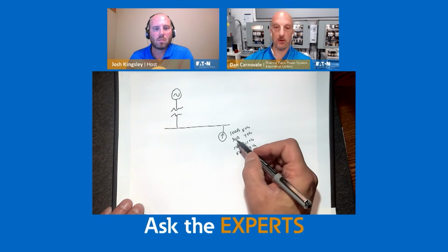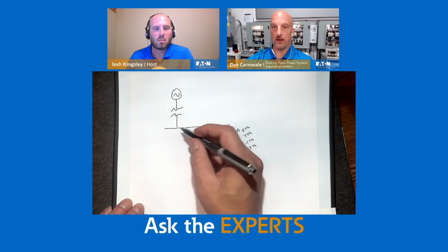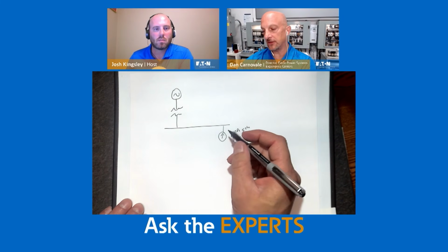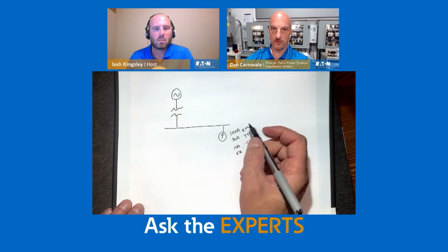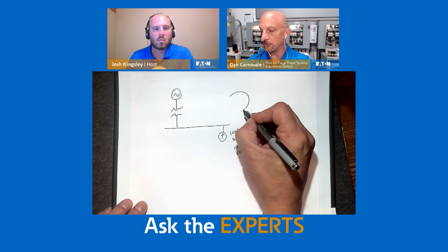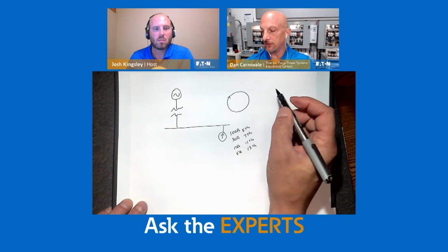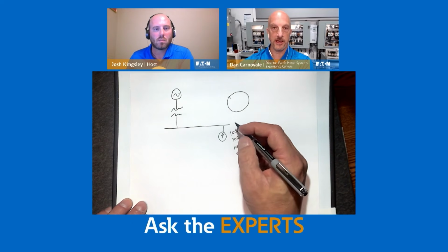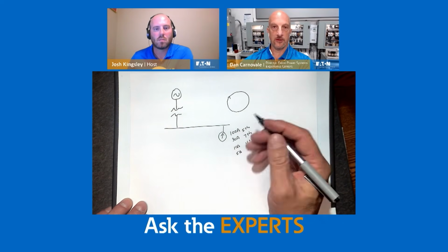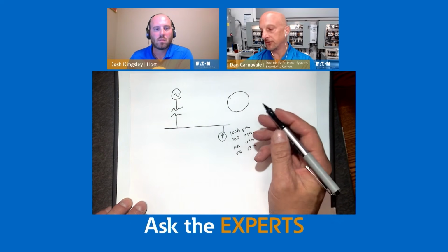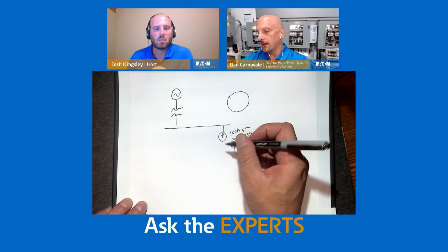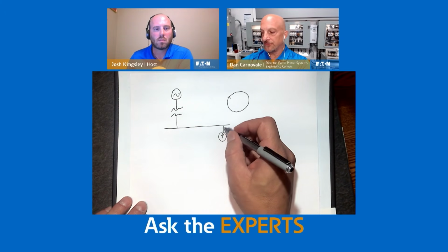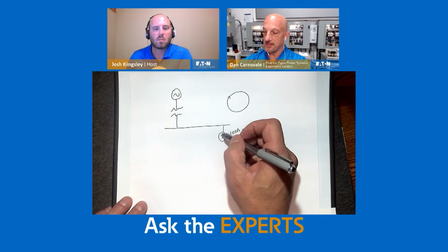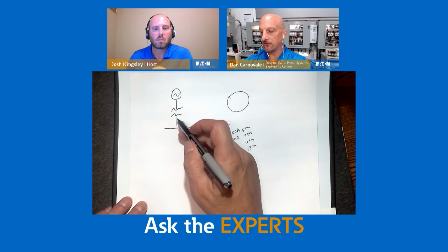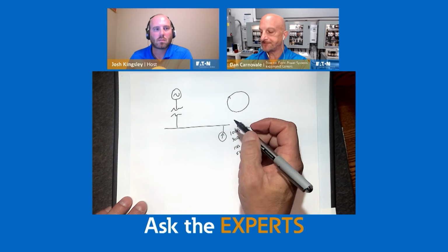Okay, current, as we mentioned, is going to flow out and flow back. And one of the things that I think is very important to understand is current has to flow in a loop. So no matter what, it's going to flow in a loop. So if current is created, meaning we allow that drive or that load to create the current, it's going to flow in the loop and come back. So where does current want to flow? It wants to flow the path of least impedance. And in this case, it only has one path. So it flows out on phase A, back on B and C, for example.